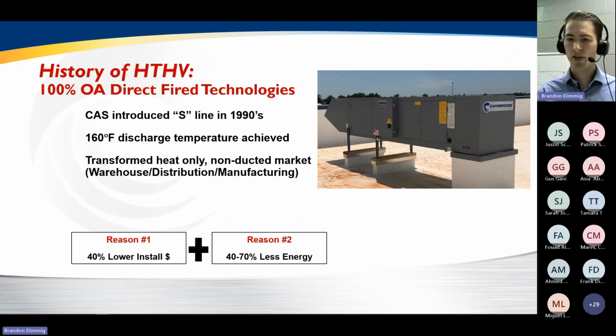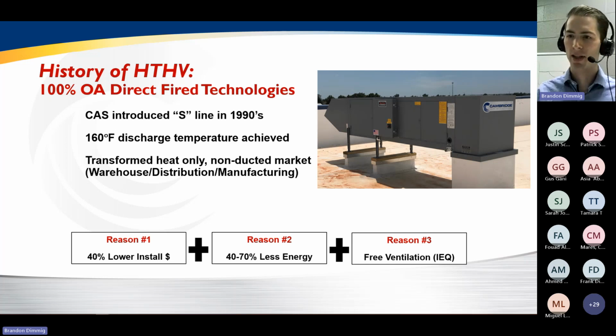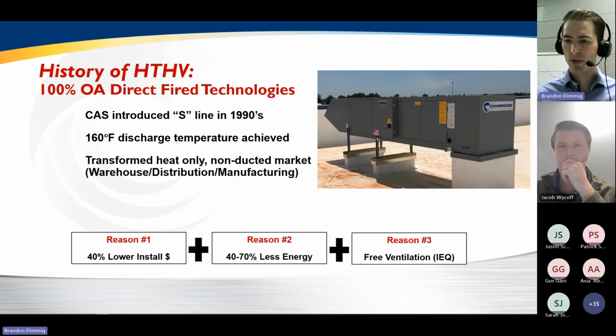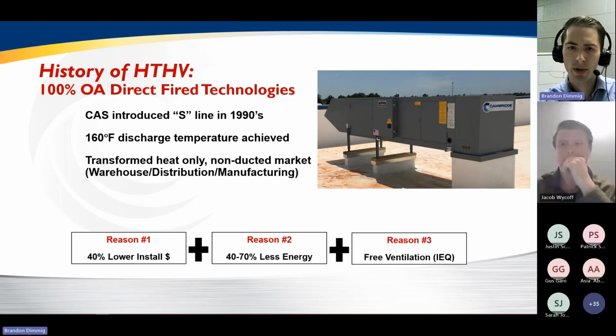The second is, of course, energy efficiency. The high temperature discharge, and we're going to go into why that is really important, and the direct fired nature of the equipment leads it to being a very efficient usage of natural gas. Being 100% combustion efficient, 92% thermally efficient, basically getting all the heat possible out of the natural gas that's coming into the unit. And so people saw their utility bills decrease as they switched over to this equipment. And then the last part is the ventilation aspect. It's a 100% outside air unit, and so now we have consistent outside air ventilation that was improving the indoor air quality of facilities that had historically relied on natural infiltration. And there's some pros and cons to natural infiltration that we'll get into a little bit later.